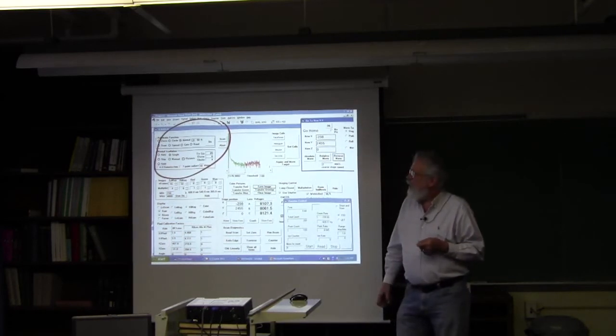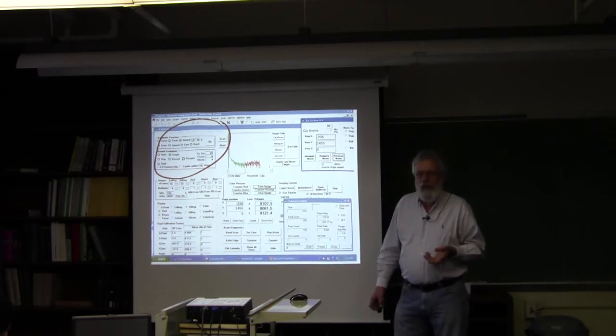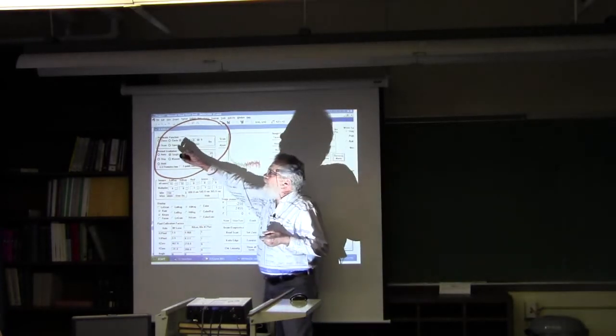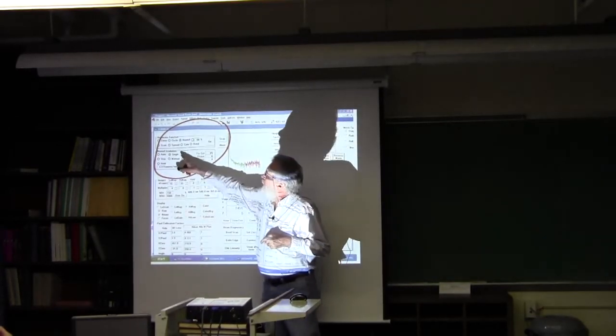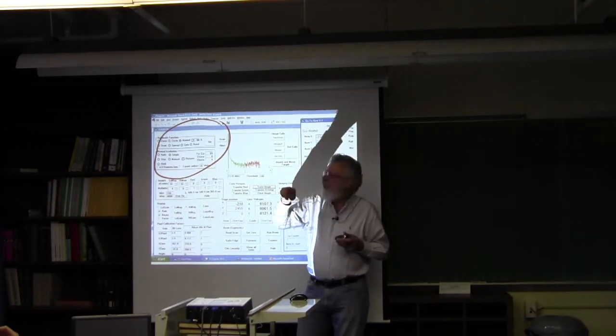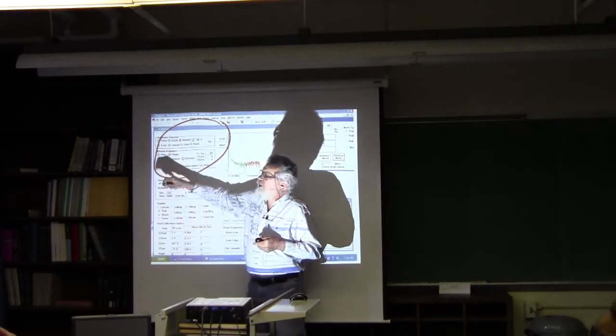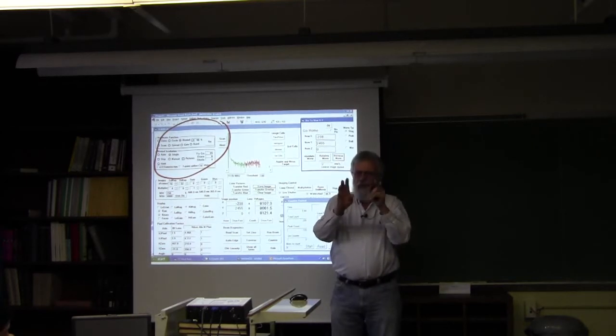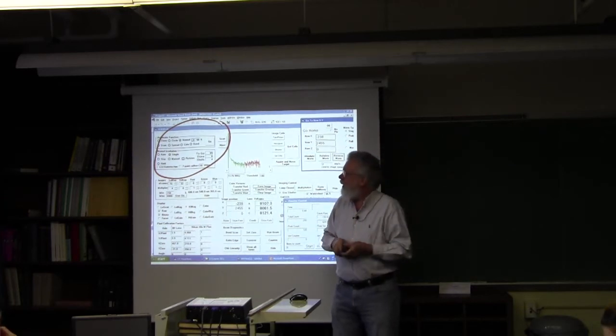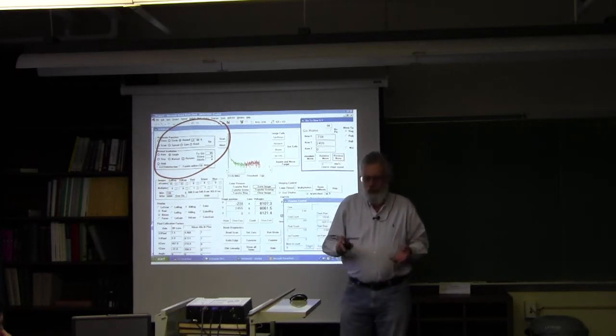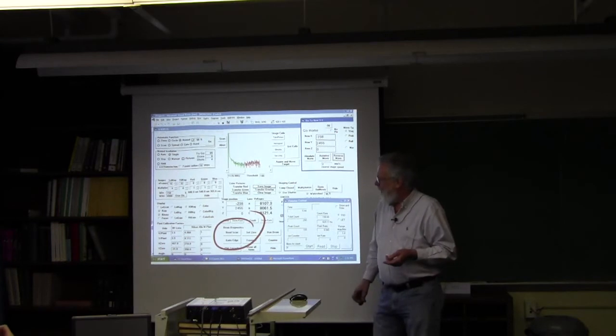This is for controlling our radiations. Normal radiation is hitting the center of every nucleus you find. Cyto is to find nuclei and then shoot outside the nuclei where you would expect the cytoplasm to be. Band is something where you shoot across the middle of a sample in a line of chosen width. We had a fellow visiting and we wanted to do bystander effects with a circle, so you have your dish with the cells in it, you draw a circle within that and then shoot a certain number of particles around on that circle. If you have another scheme, we'll program it in for you.